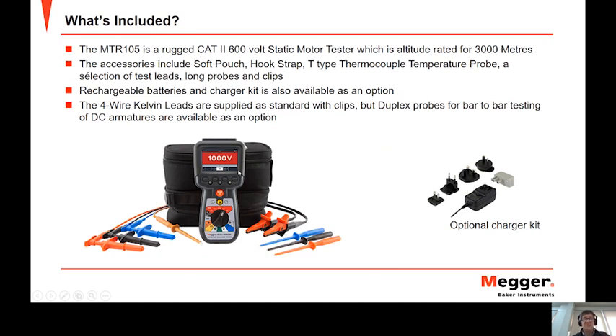The standard unit is powered by AA batteries, and we have an optional recharging kit which comes with rechargeable batteries. The other option we have is, instead of the 4-wire Kelvin clip lead set, we can also have a duplex probe kit. That is for measuring bar-to-bar winding resistance on DC armatures, for example, where you have your two probes on each bar measuring the resistance across.